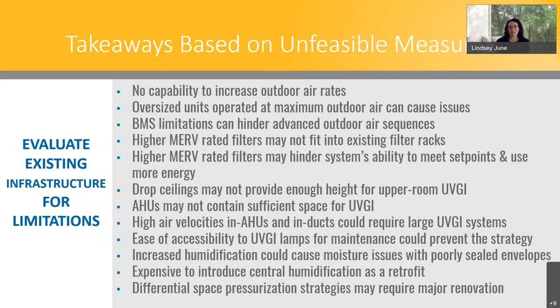On the other hand, oversized units that do have capacity to significantly increase outdoor air rates can pose issues meeting comfort set points and proper system functionality if outside air is increased to the max possible. Physical restrictions may be typical with custom built-up air handling units and fan coil units or unit ventilators, such as being able to accommodate higher MERV rated filters. Increased MERV filtration levels doesn't always introduce a pressure drop or capacity issues; units with VFDs can moderate accordingly for low impact.